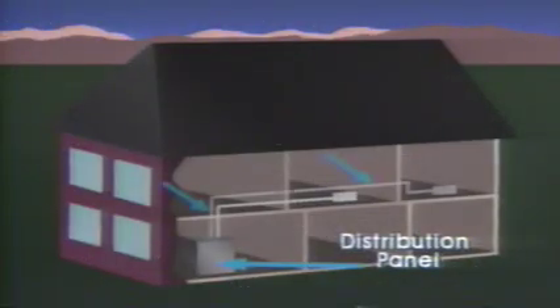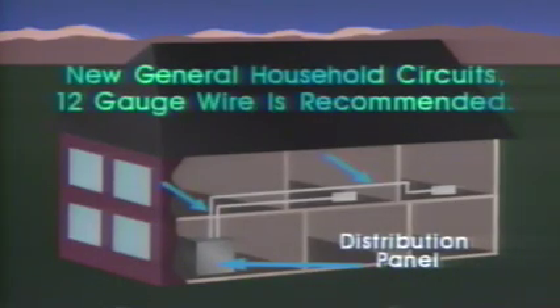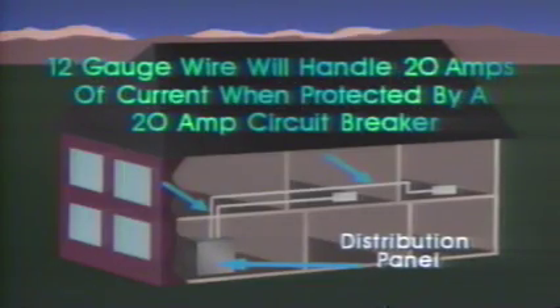When adding a new general circuit, most codes today recommend number 12 gauge wire, which will handle 20 amps safely and can be protected by a 20 amp circuit breaker. This is due to the increased use of modern appliances such as TVs, hair dryers, microwaves, curling irons, and kitchen appliances.